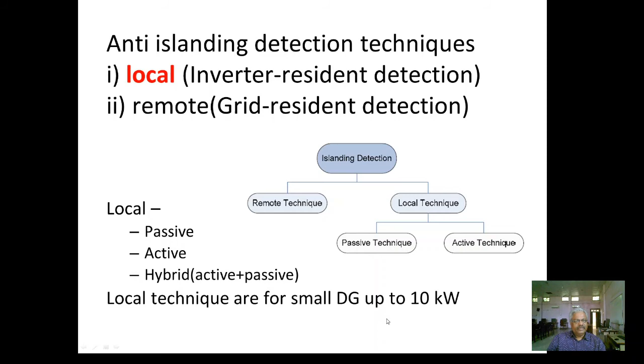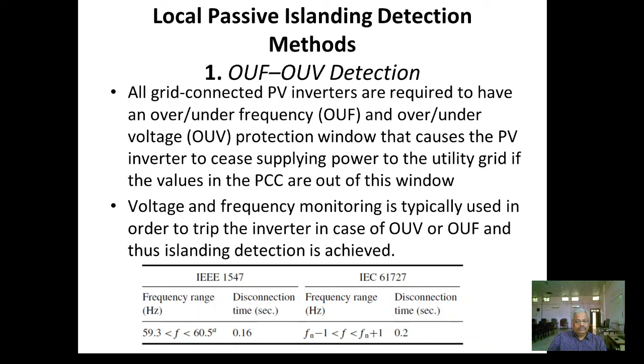Now we will see the local passive islanding detection methods. These methods we are supposed to add in addition to the voltage and frequency detection. The first is OUV and OUF detection. We have seen this as per standard 1547. This is the frequency range, 59.3 to 60.5. Disconnection time 0.16. IEEE reduces the time from 2 seconds to this. And for IEC, the disconnection time is 0.2 seconds. This is the frequency range.